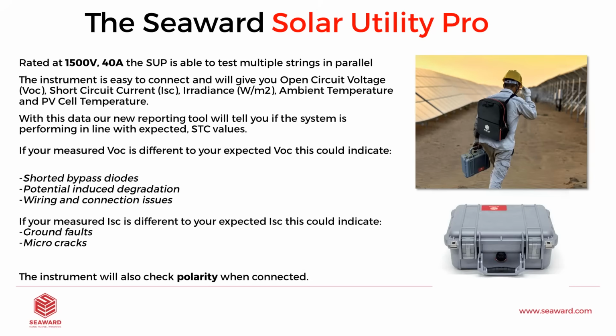The instrument will also check polarity when you connect it, which is one of the biggest problems I see with regard to commissioning systems. So this Solar Utility Pro is really born from our experience with our previous instruments, our PV150, our PV210. They're rated at 1000 volts, 15 amps. And one of the biggest problems I had with those instruments was that my users were overcurrenting the device. So they were putting more than 15 amps through that device. So that told us that, right, we really need a high upper limit for this instrument. So this is why we went for 1500 volts at 40 amps.